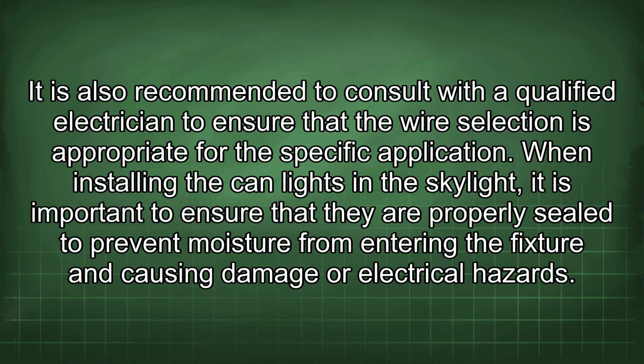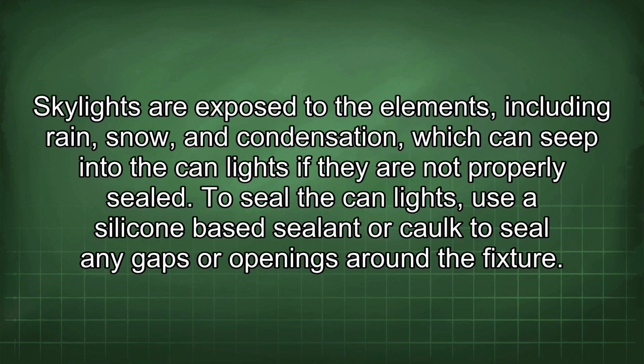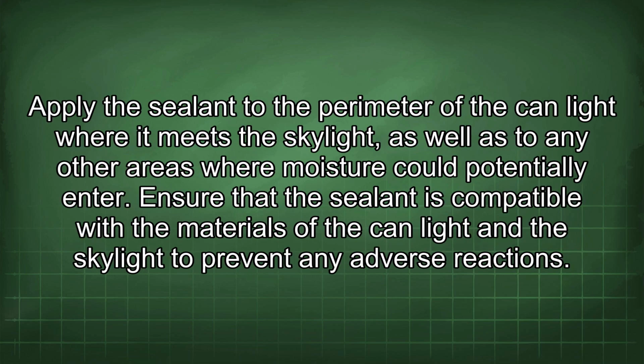specific application. When installing the can lights in the skylight, it is important to ensure that they are properly sealed to prevent moisture from entering the fixture and causing damage or electrical hazards. Skylights are exposed to the elements, including rain, snow, and condensation, which can seep into the can lights if they are not properly sealed. To seal the can lights, use a silicone-based sealant or caulk to seal any gaps or openings around the fixture. Apply the sealant to the perimeter of the can light where it meets the skylight, as well as to any other areas where moisture could potentially enter.